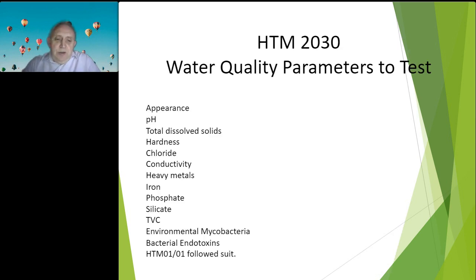So HTM 2030, of which HTM 01 followed suit - what sort of parameters do we look for, what sort of parameters do we test? Well, we look at the appearance, we look at the pH, we look at the total dissolved solids in the supply, we look at the hardness, we look at the chloride content, conductivity, heavy metals, iron content, phosphate, silicate, TVCs, environmental mycobacteria, bacterial endotoxins. So as you can see, there's a host of parameters that we need to monitor, to control, to make sure our surgical devices are safe. The appearance is not compromised, the device is not compromised.